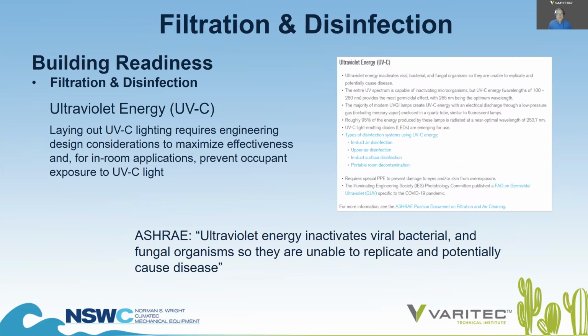Filtration and disinfection goes on to ultraviolet light technology, laying out UVC lighting. It requires engineering design considerations to maximize effectiveness and, for in-room applications, prevent occupant exposure to UVC light. You have to make sure that your devices are properly designed and laid out to meet the application for UV light to be as effective as it can be. ASHRAE does state, though, what is very attractive about UV light: it states categorically that ultraviolet energy inactivates viral, bacterial, and fungal organisms, so they are unable to replicate and potentially cause disease.